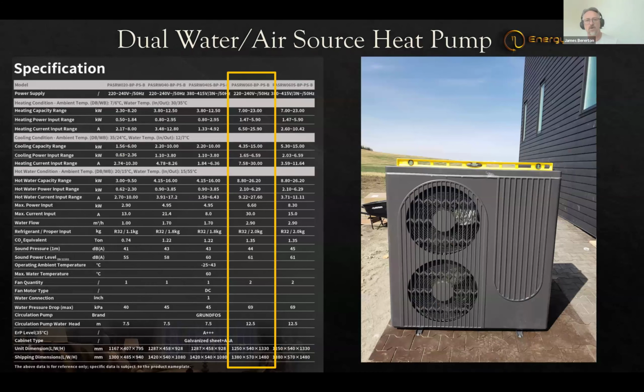This is our dual water-air source heat pump selection, in the yellow box. You can see some of the performance there—this works down to minus 25 quite readily, and uses R32 as the refrigerant. At the time we were ordering and building this, propane R290 was not yet considered legal in Canada. Now there's an interpretation ruling on the current code that would consider outdoor R290 heat pumps viable, and they would perform even better than this heat pump.